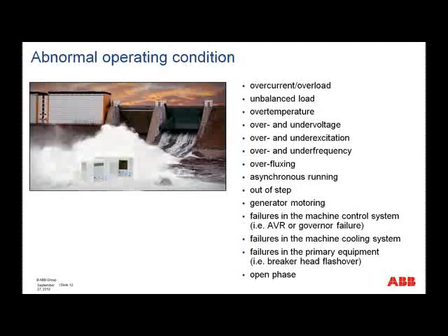Then we also have a number of abnormal operating conditions. And these, although they may not need to immediately trip the generator or the unit transformer, they need to do so at some time. These conditions cannot continue. So if they do persist, then we would need to, at some stage, trip out the plant.